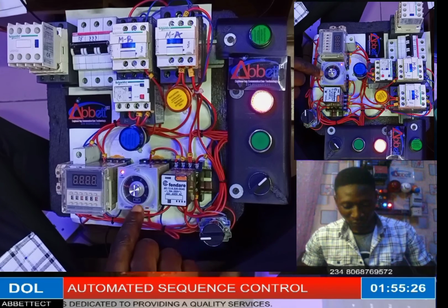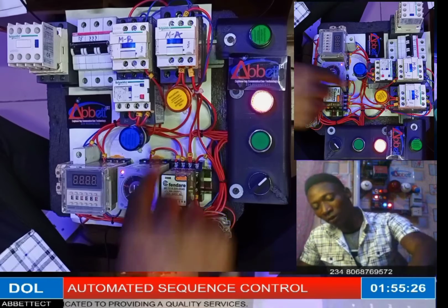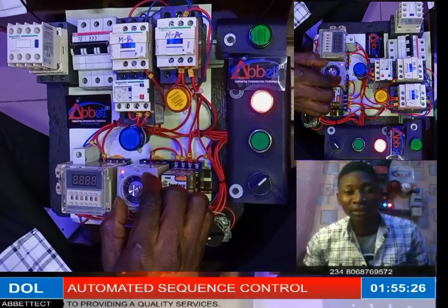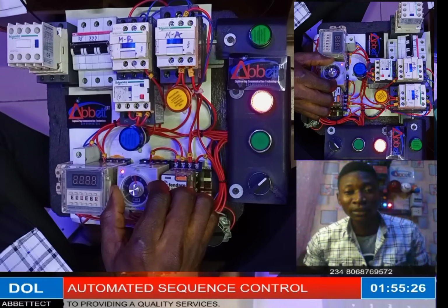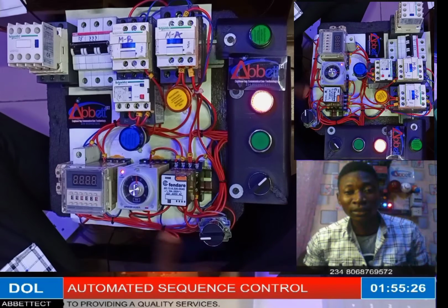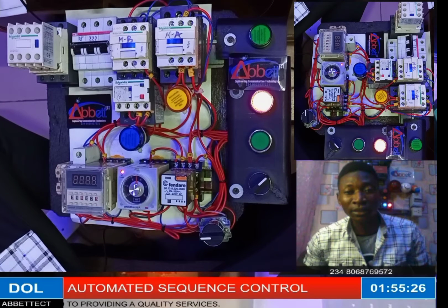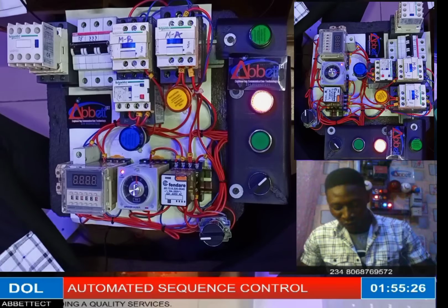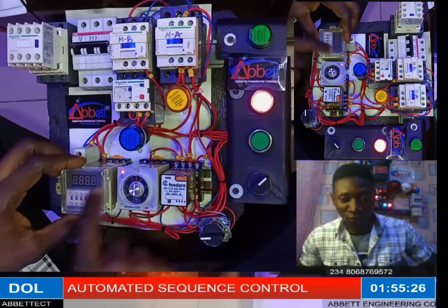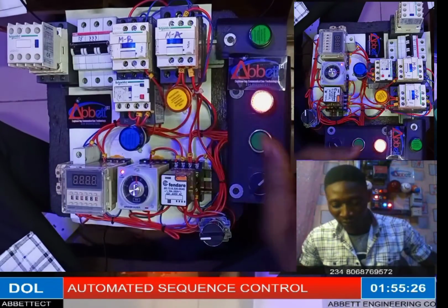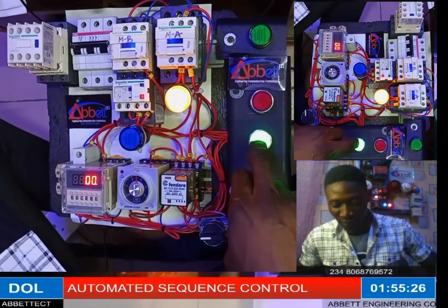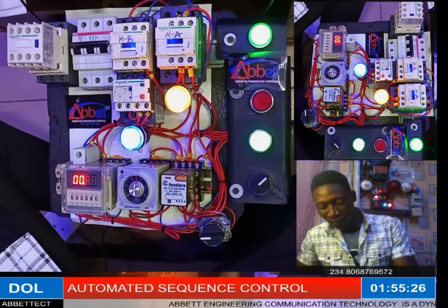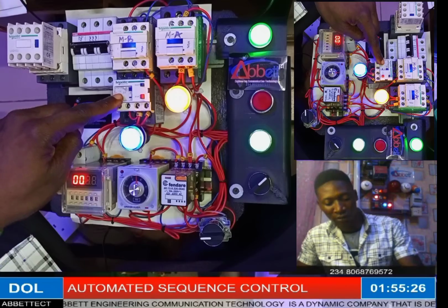So if I want to increase the stopper timer for motor A, I can simply increase it here. You understand? Let's increase it now. I've increased it to, let's say, 1 minute. You understand? So this one too. Okay, let me just test this one. Yeah, let's operate it again. You see now? Motor B is closed.